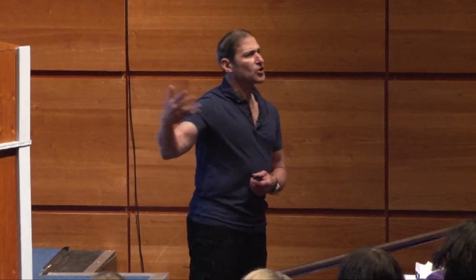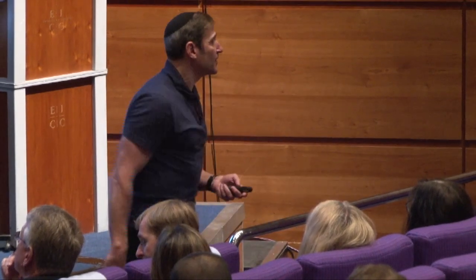I don't know. Which manufacturer are you using? Which coil? Which transmitting coil? Stop telling me about the receiver coils. From a point of view of burns, nobody cares. The only thing I want to know is which one is the one that's going to transmit these potentially harmful energies into this patient. The receiver coil is, stay with me here, receiving, hence the name. We're worrying about the transmitting coil.